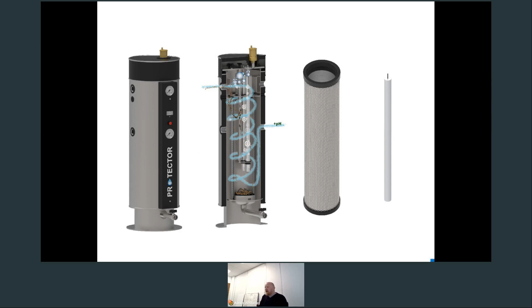Then if you look at the third image, you can see the magnet and the anodes running almost the length of the inside of the vessel. The magnet sits in front. It's a very powerful neodymium magnet which sits in front of the 2 anodes, and that magnet and the anodes running the length means that you get a lot more efficient contact with the surface area of the water and the anodes and the magnets, and that means that you're pulling out the magnetite from that water at a lot faster pace. It's also protecting the anodes and ensuring that none of that magnetite goes onto the anode surface, therefore restricting its efficacy.